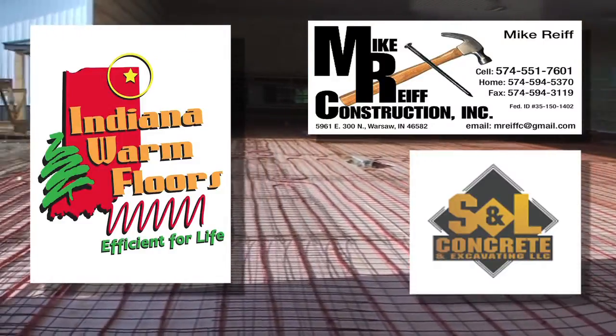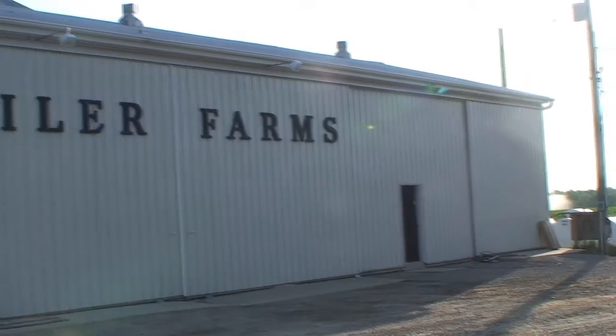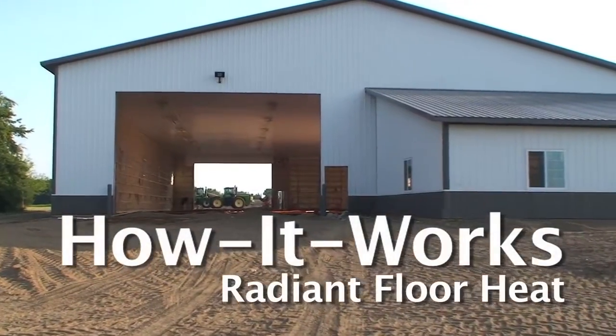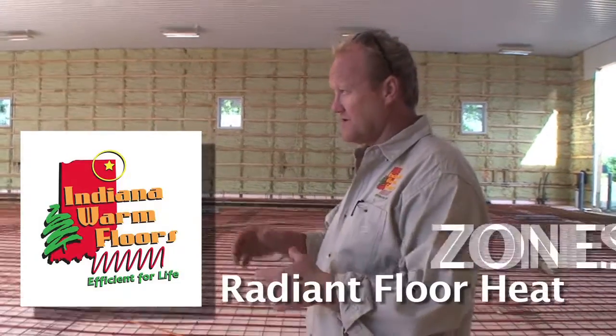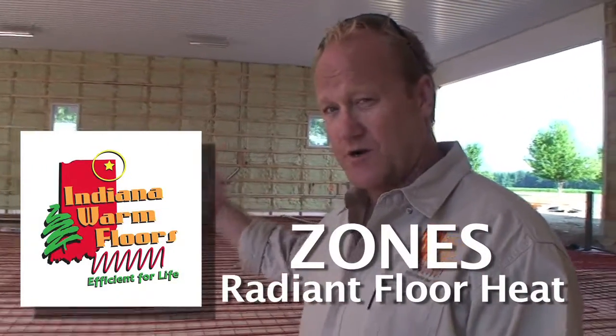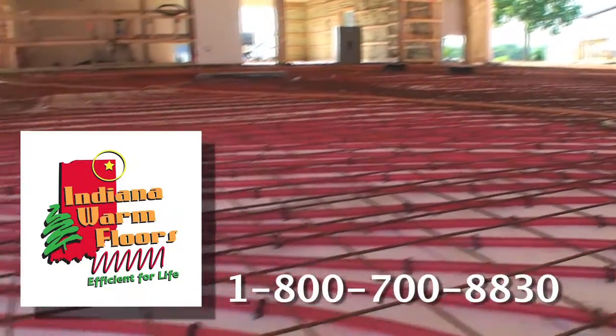It's pretty impressive to look out there and see all those red tubes. That's a lot of tubing. This room is approximately 13,000 square feet. We split it up into four zones — one that allows us to not have a real big hot spot because of one big manifold, but it also gives him the ability to turn off sections or turn back sections that he won't be working in that day, and that helps promote efficiency.